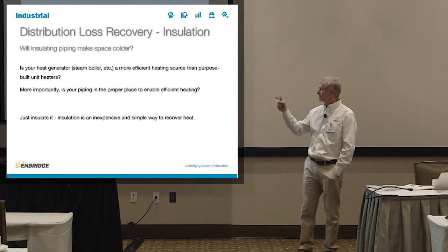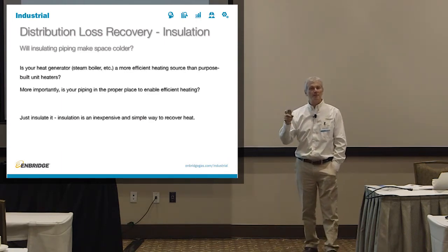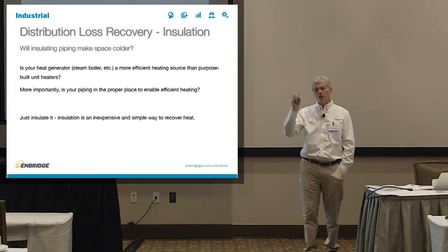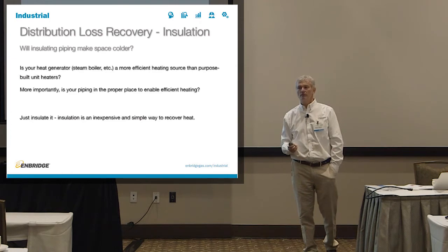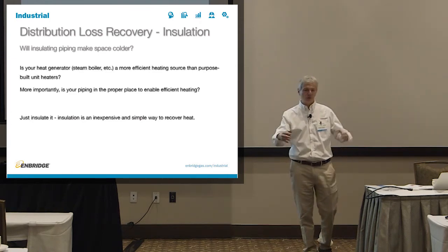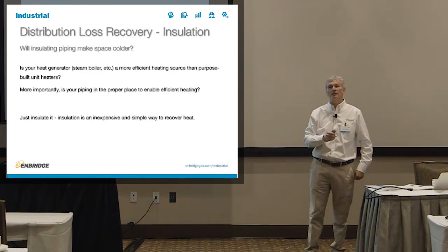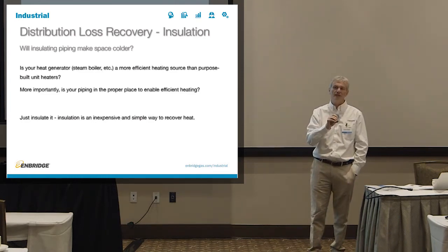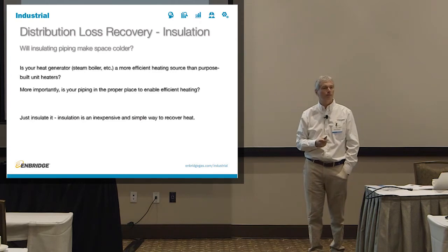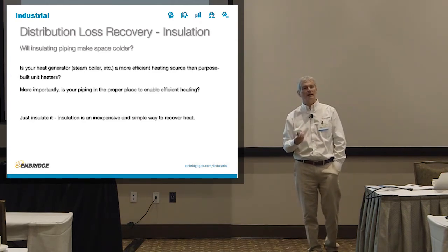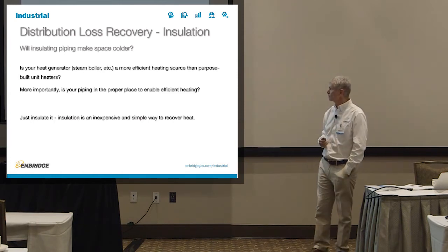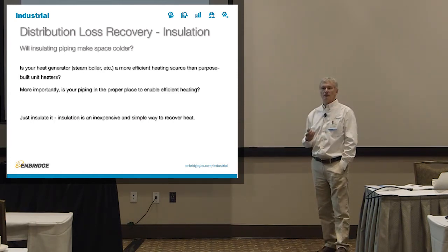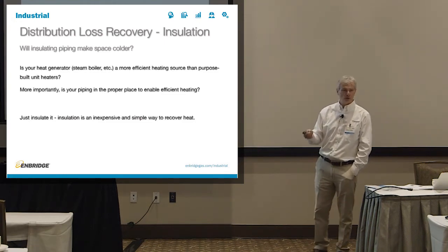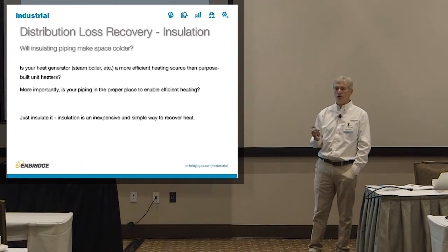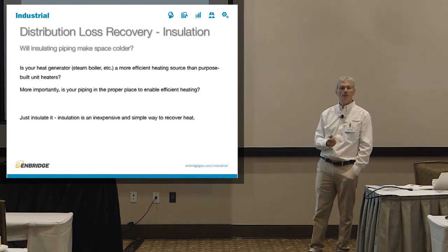Exactly. Same thing here. Usually you have steam piping out of the floor level, closer to the ceiling, because you don't want people to get burned. That's out of the way of the regular production space. So usually you have them run next to the ceiling. So even if they're contributing to the heat in the space, they're really heating the ceiling area. And what do you do with the ceiling area heat? You exhaust it out of the ceiling. So you're really not gaining a heck of a lot in the heating value of those non-insulated things. The other thing is, is that really the most efficient way? Is that heat where you need it? No, typically not. So just insulate it, get it over with. Even if the heating requirements go up, you're better off.